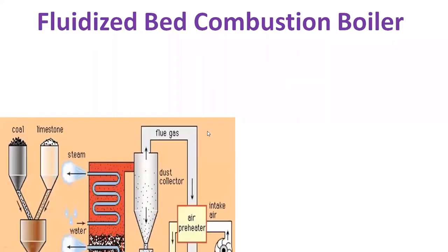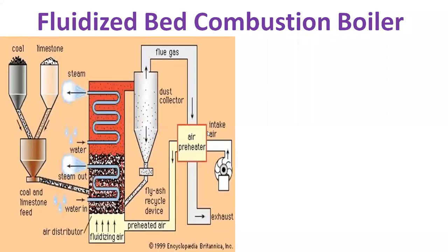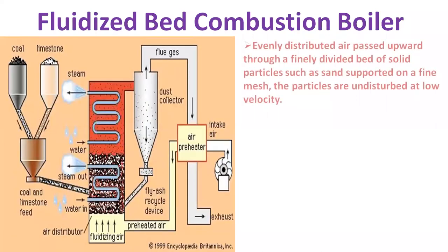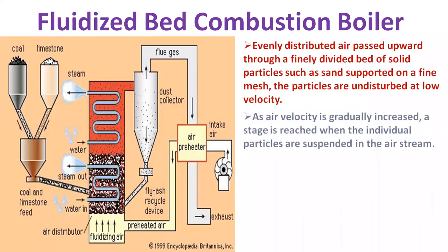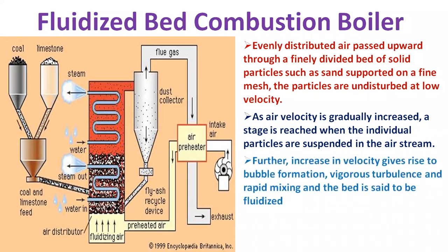Then we have a fluidized bed combustion boiler. When an evenly distributed air or gas is passed upward through a finely divided bed of solid particles, such as sand supported on a fine mesh, the particles are undisturbed at low velocity. As air velocity is gradually increased, a stage is reached when the individual particles are suspended in the airstream.